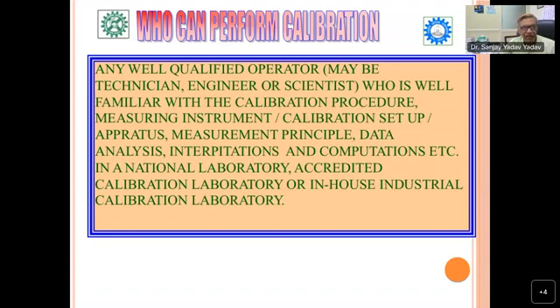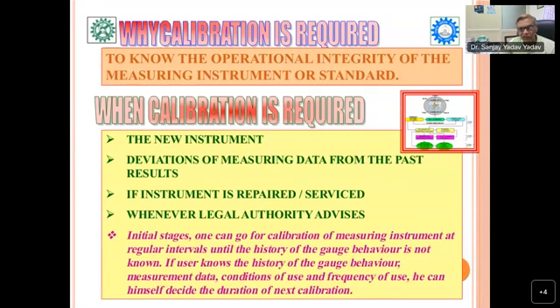So who can perform? Any well-qualified operator, maybe a technician, engineer, or scientist who is well familiar with the calibration procedure, measuring instrument, calibration setup, apparatus, measuring principle, data analysis, interpretation, and computation, in a national laboratory, accredited calibration laboratory, in-house industrial calibration laboratory, etc. The third W is why calibration is required. To know the operational integrity of any instrument, you need calibration against the standard. Another W is when calibration is required, very, very important.